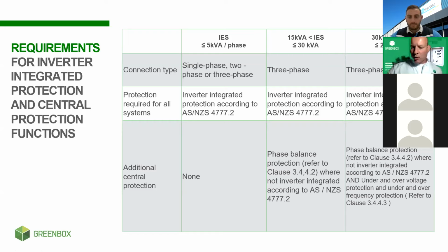Another question from the chat was the opposite — if I put on a 60 kilowatt system but add an export limit, does that solve the problem? No, it doesn't. As soon as you go over 30 kilowatts, unfortunately you have to install the grid network protection device. That's the only way around it. I hope that clears things up a bit more.